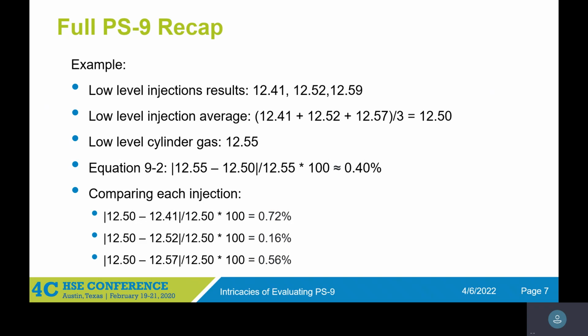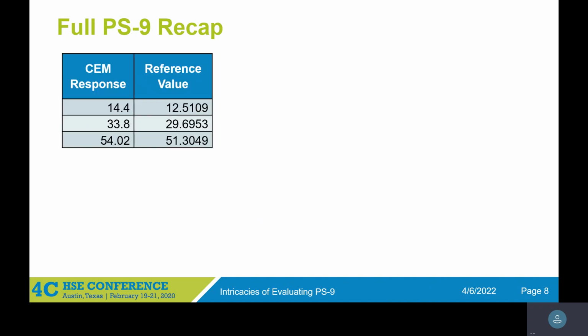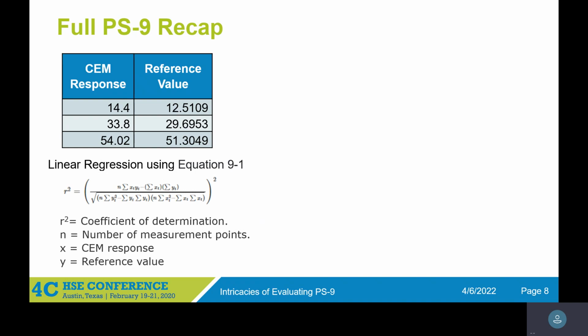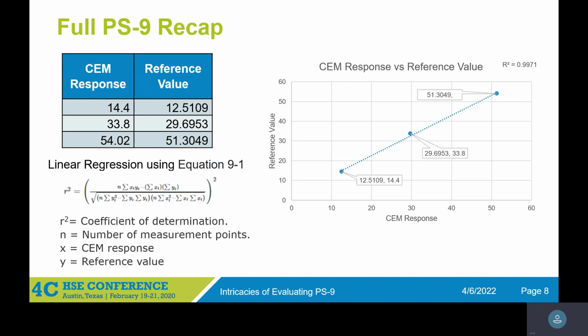We have a comparison against each injection result, and then taking all of those 3, that's when we get into doing a linear regression. Say this is kind of what our data looks like for the CEM response for that low level, then our mid level, then our high level, and the reference value for each of those levels on there. So we would use equation 9-1 to do a linear regression, which you can do pretty easily in Excel with just a table and plotting that out. And you can see we then use this calculation to get a linear regression of 0.997, which meets the requirement of being greater than or equal to 0.995.